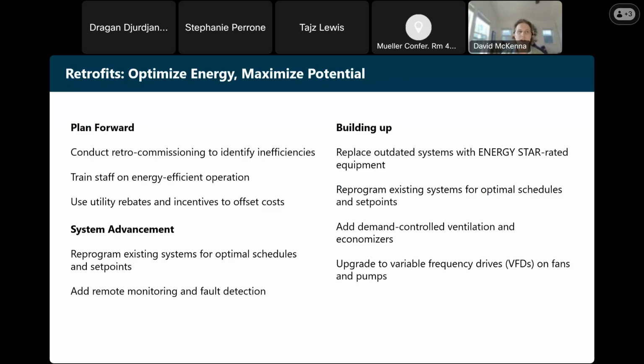Part of that, and we'll talk about this a little bit more in a second, is providing the building with sensors so that we can actually control those devices appropriately. A large part of that relies on A, the sensors, but B, the sensors being installed and calibrated correctly. When that starts to happen, the system literally gets smarter and enables us to trim, respond, and optimize that component's energy usage. So again, some examples here on how we can accomplish that. And we'll talk a little bit more about that as we progress.